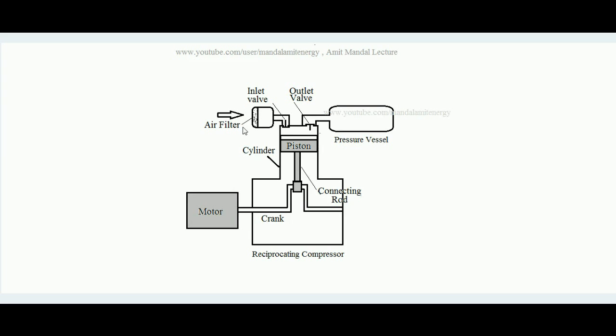There is an air filter whose job is to screen out dust and debris from the air, because these can damage the internal parts of the piston-cylinder system. Overall, the piston reciprocates to and fro between the top dead center and bottom dead center, taking in low pressure air from the atmosphere through the air filter and pushing it into the pressure vessel at raised pressure — this is done continuously by the reciprocating compressor.